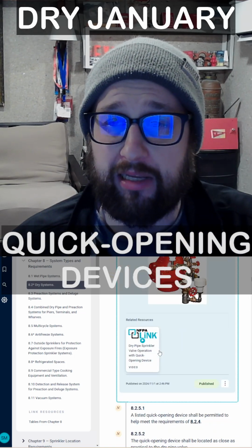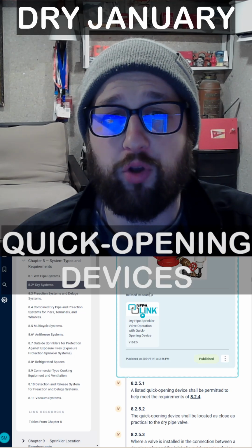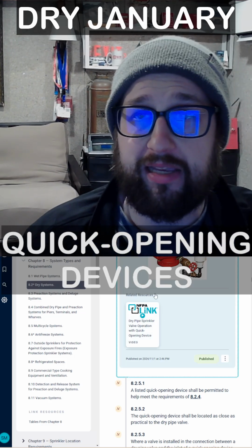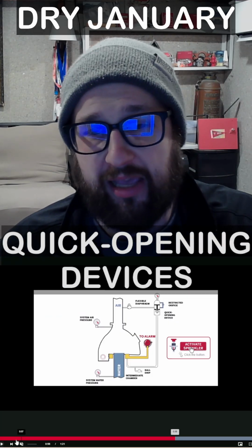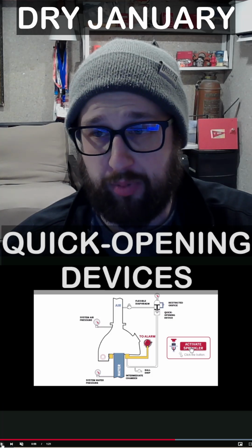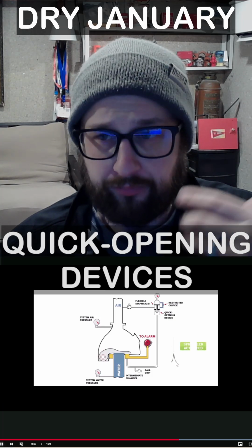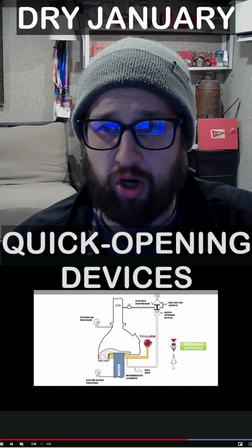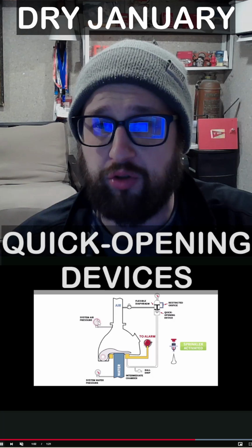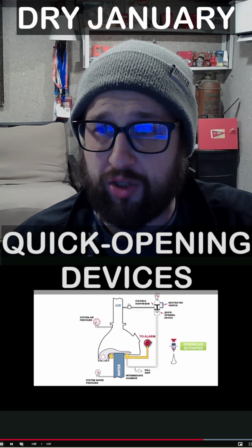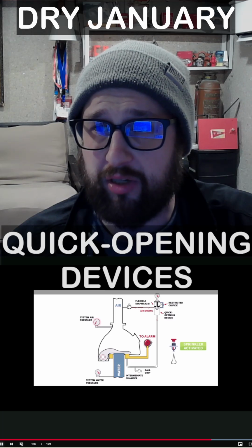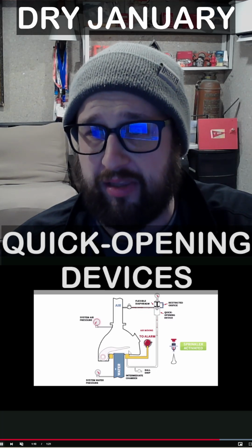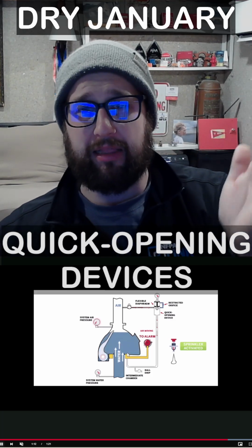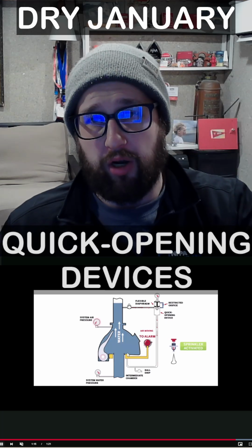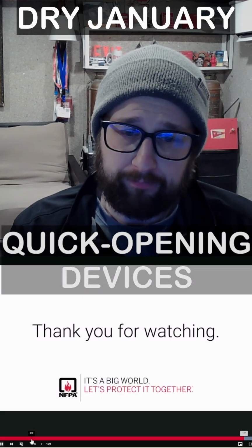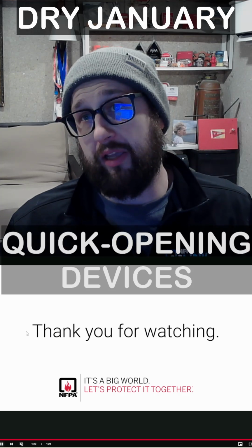If you look in the enhanced content, there's actually a video here that goes over a lot of the detail on what a quick opening device is. I'm going to show, just at the end of the video, the operation of the quick opening device. You see here that the sprinkler is going to discharge air. The system air pressure is going to drop. And then this is the quick opening device here. The air pressure is going to drop in there, and then the air is going to move into that intermediate chamber and allow that clapper to open quicker and allow water to discharge out that sprinkler system. So that's an example of a quick opening device.